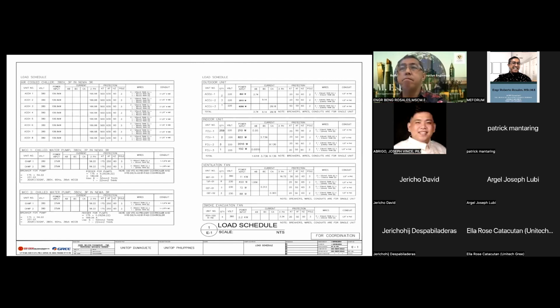Now, if you're gonna check on the left side, yung load schedule natin, we have 8 chillers with 110 kilowatt. Hindi ko pa siya ginagawang KVA, pero based on the conversation namin ni Surfing, I think gagawin natin power factor is 0.9. Correct me if I'm wrong, Surfing. Pero if you're gonna convert it to KVA, i-divide niyo lang siya ng 0.9. Yun na yung KVA natin.